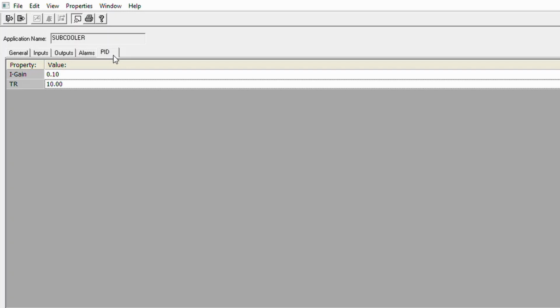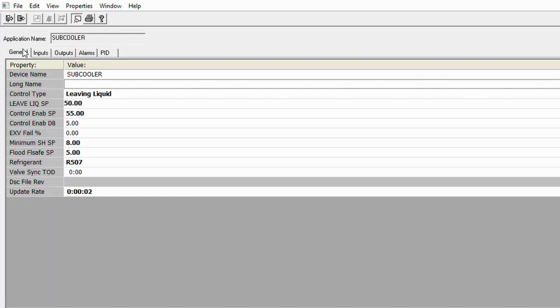Don't make any adjustments when stuff's in defrost. You should also do this under a decent load, like 90-degree liquid. If you've got to crank up your head pressure, then do so. That's what I recommend if you're going to tune these PID loops. Just remember, go slow, little changes. Little changes make big changes.